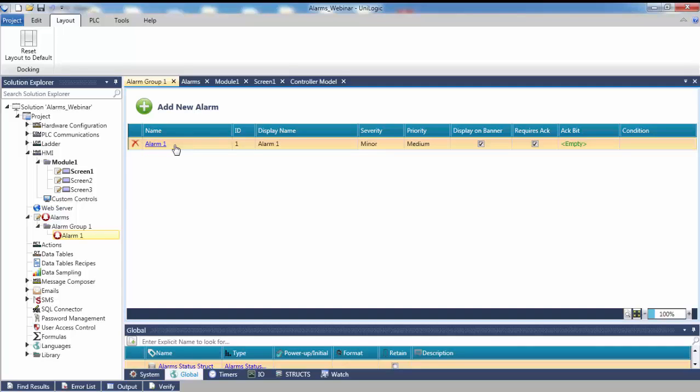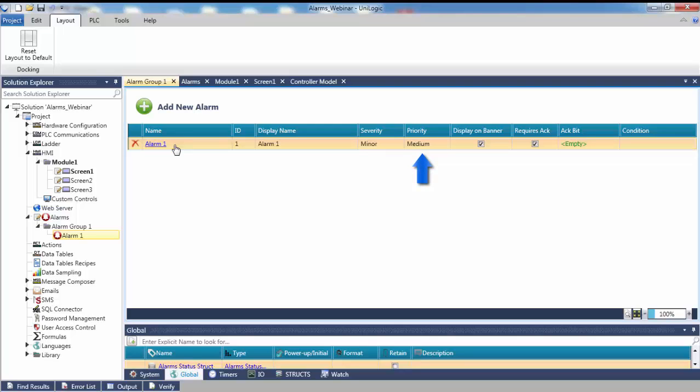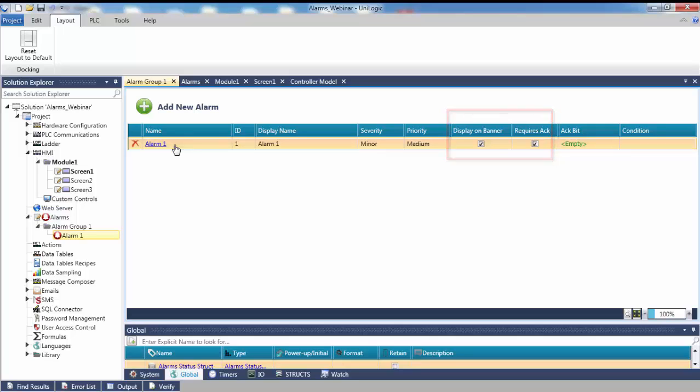Each alarm in a group has seven unique properties: an ID, which is a unique number assigned by the system that cannot be edited or modified; a Display Name, which will identify the alarm in both the Alarm Summary and the Alarm Status Viewer widget; a Severity, which is the extent to which the condition impacts the program; a Priority, which is the order in which we should resolve conditions; and finally, use check boxes to determine whether an alarm is displayed on the banner and if it requires an acknowledgement.